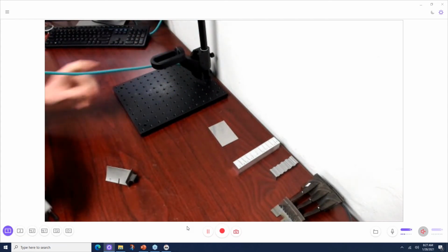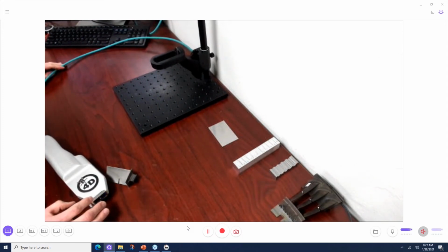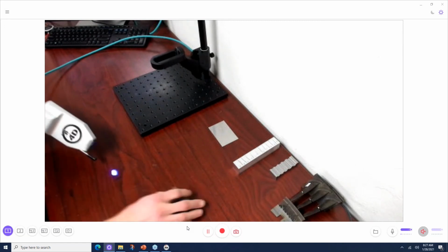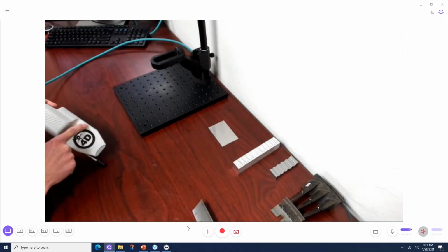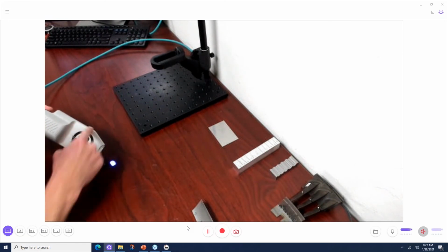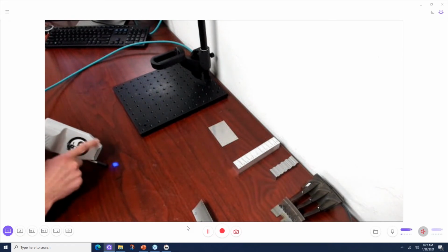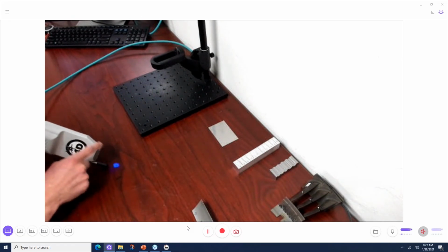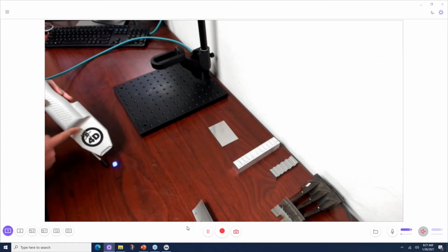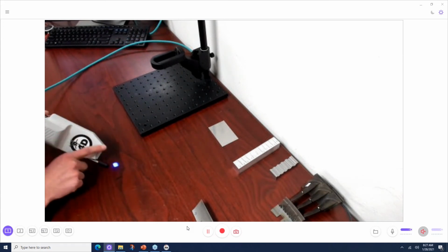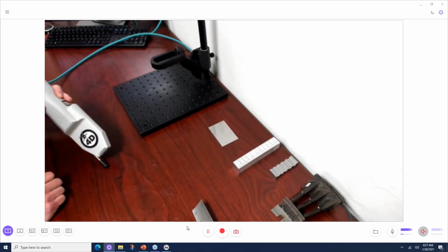Have you gone over the geometry of the device yet? How the light comes out? Yeah. So this light is coming down from an LED through some lenses, coming at an angle down through here, kind of just along, parallel to this nose piece right here, down out, reflects off a surface and back to a camera right here. So it's coming at a little bit of an angle, reflects off a surface and back to this camera. That's the path of the light.